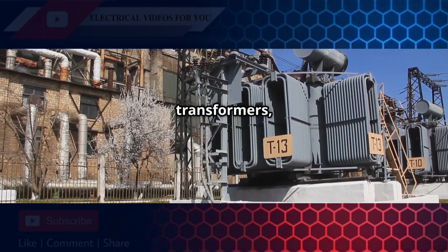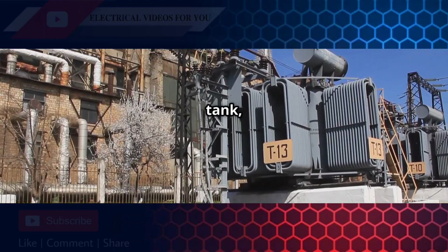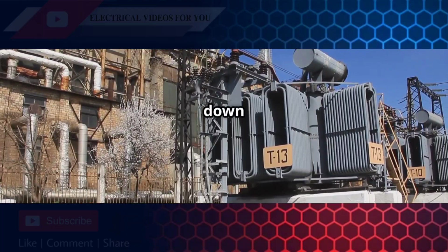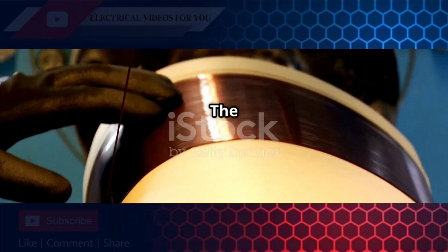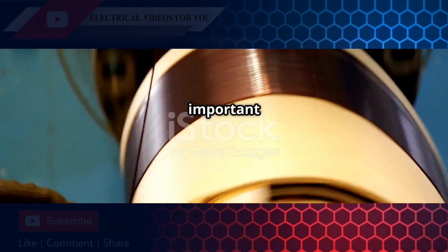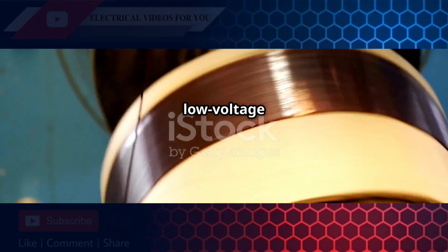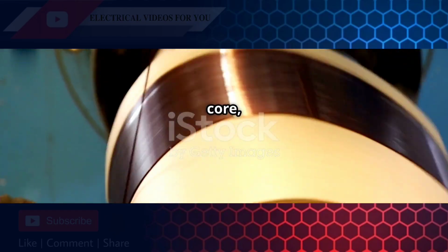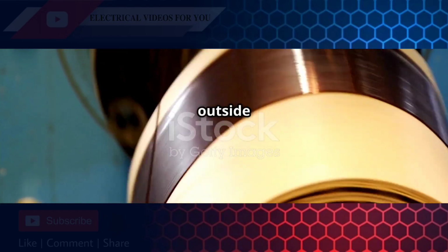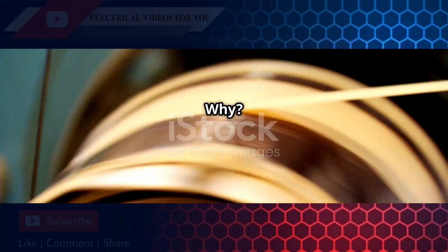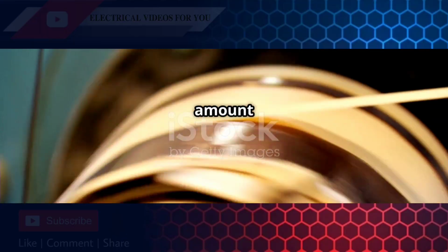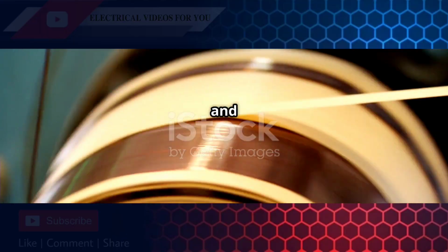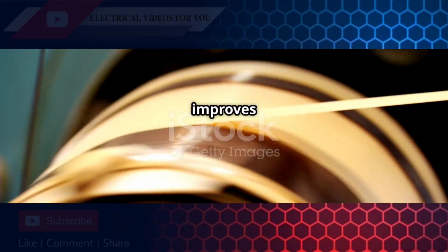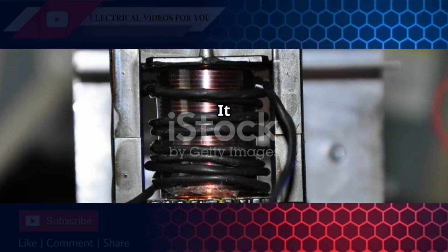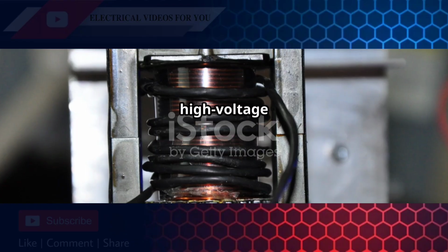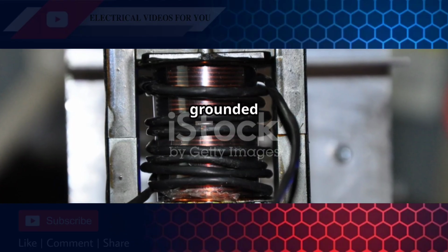In larger transformers, all these parts are housed in a protective tank, often filled with oil to help cool it down and provide insulation. The placement of these windings is very important for efficiency. Typically, the low-voltage winding is placed closer to the core, and the high-voltage winding is wrapped around the outside of the low-voltage winding. Why? This arrangement helps to minimize the amount of magnetic flux that leaks out and doesn't link with the other coil, which improves the transformer's performance. It also makes it easier to insulate the high-voltage winding from the core, which is usually grounded for safety.